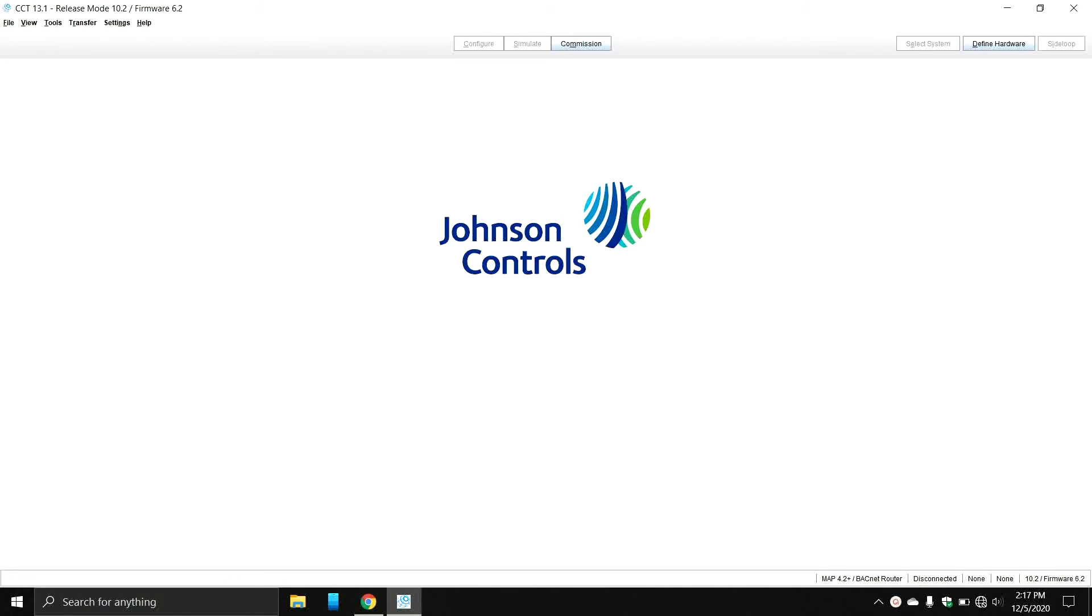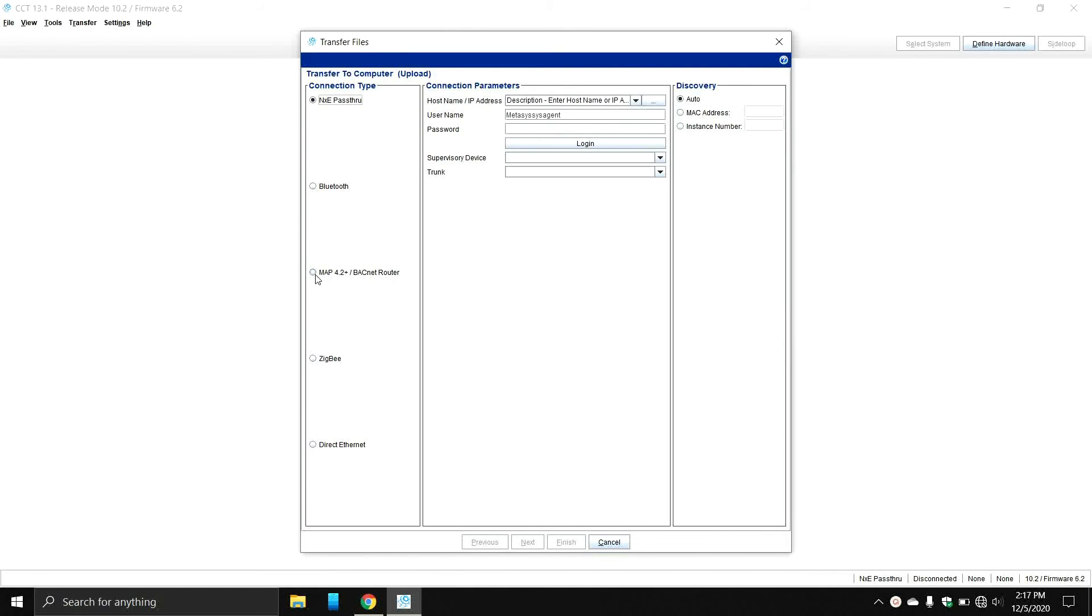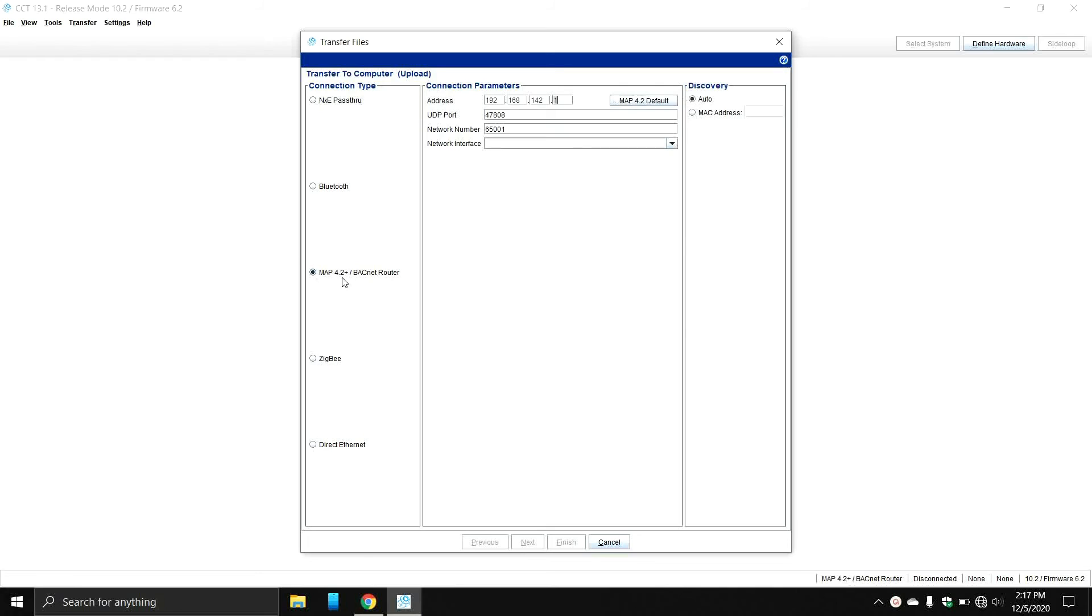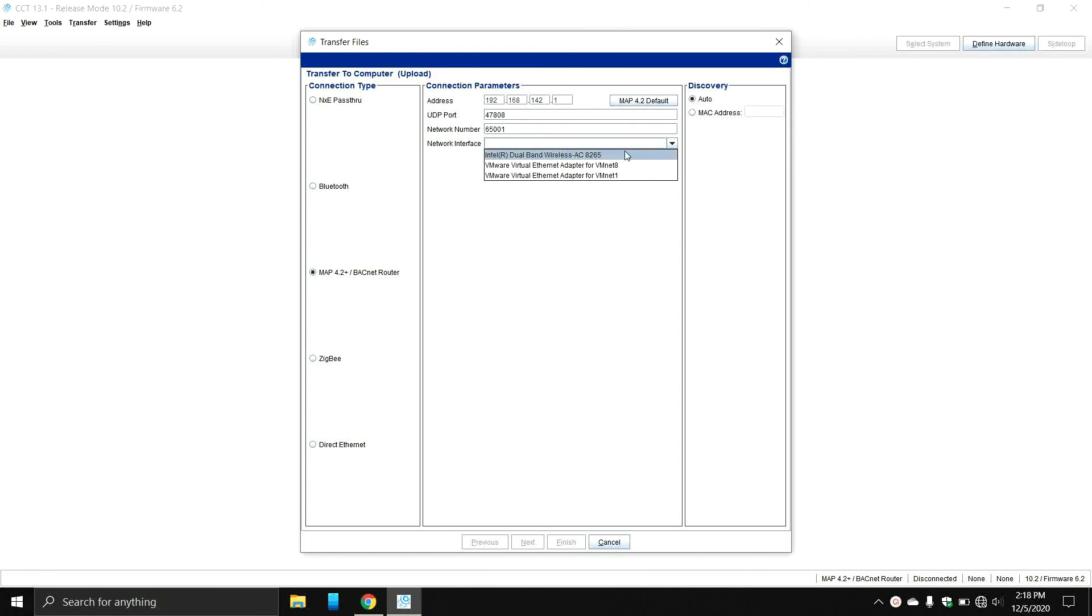Once you're connected to your MAP tool and you're in CCT, the next step would be to test to see if you can upload it. You're going to want to make sure you're right here on the MAP 4.2 BACnet router. Make sure that that circle is checked. You're not on Bluetooth or NXE passthrough. You're going to want to click on MAP 4.2 default and it should fill in these four right here with the IP address, UDP port, and network number. In older revisions of CCT, this MAP 4.2 button actually doesn't exist, so you might need to write down these numbers if you ever need to fill these in manually on an older version of CCT.